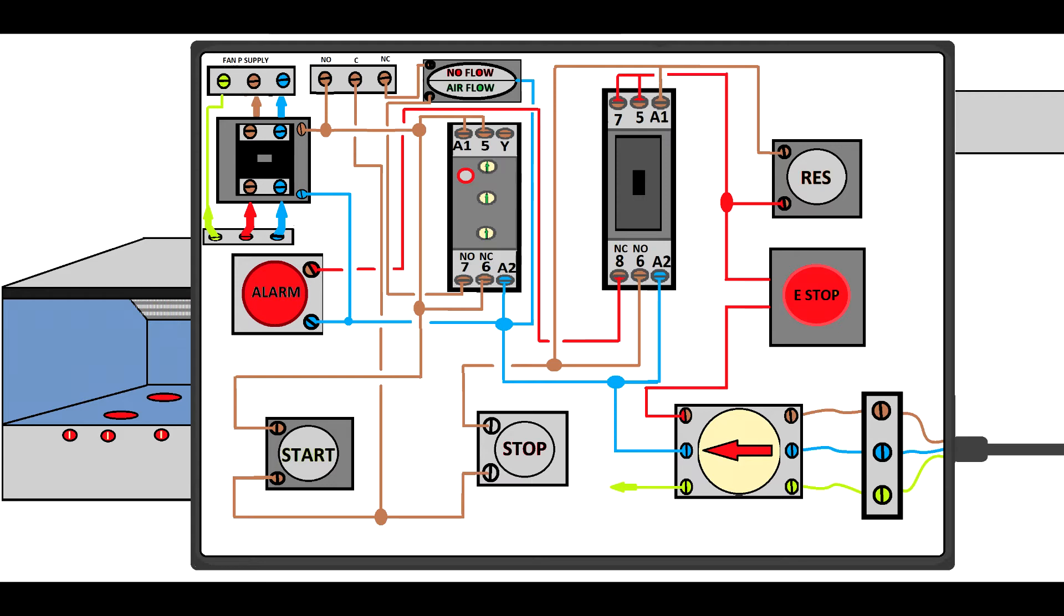Now the power goes to the main inputs into the relay, but the relay is not activated because if you look at the reset switch, there's another wire which is supposed to give power to the A1 of the safety contactor. Once you press that one, the contactor is activated and you'll see a lot of red wires come on. This provides power to the differential pressure switch which is on the top.